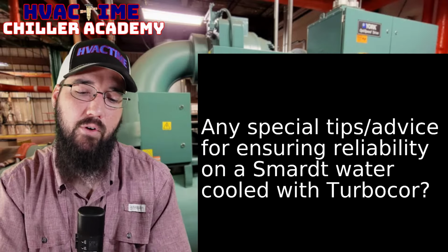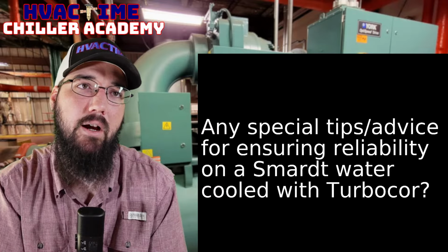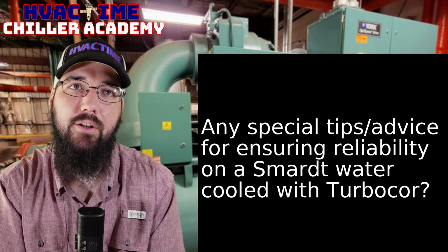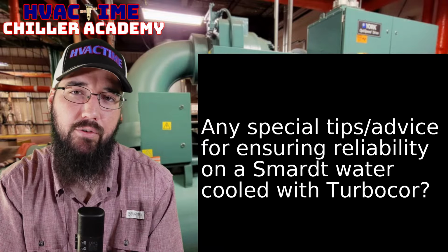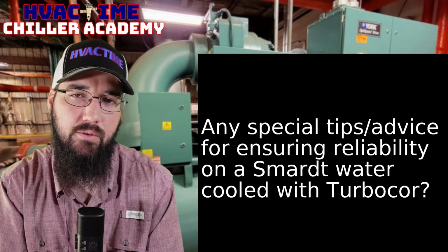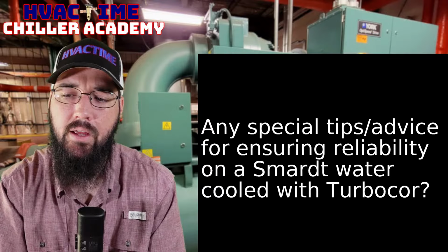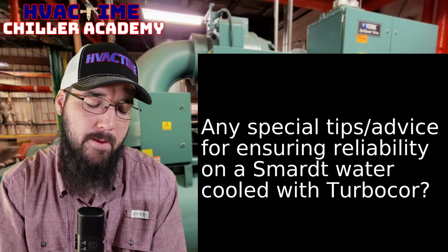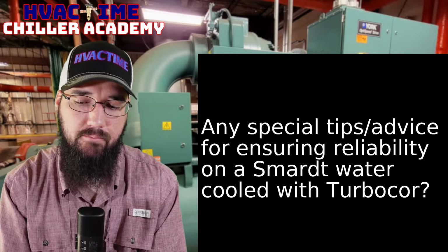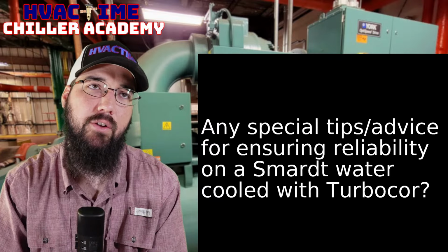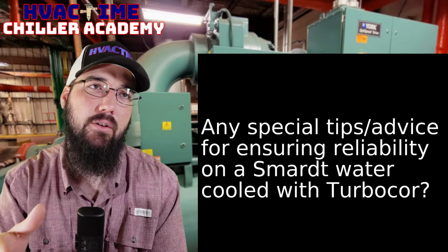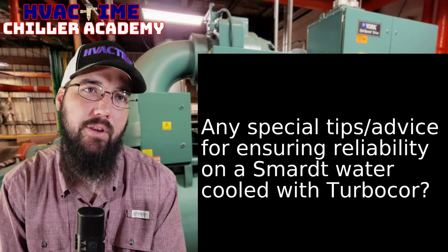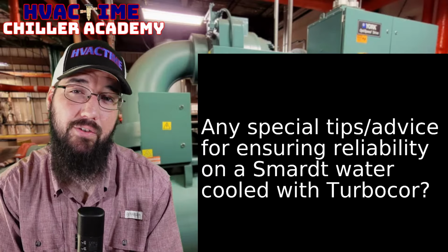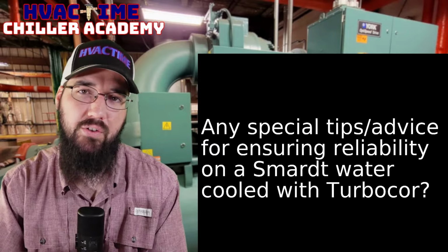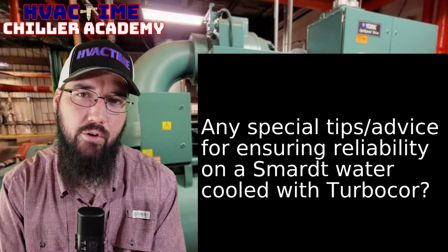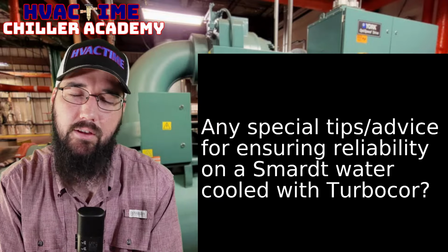So from a cold start, you could get about, I don't know, 60 to 120 seconds maybe out of that compressor before you start running into inverter overtemps. That's the primary alarm I always dealt with. And then once it overheats once, from there forward until it's able to fully cool down, you're looking at maybe 20 to 30 seconds of runtime per cycle, right? So if you're trying to correct for an inversion, that's what makes it such a pain.